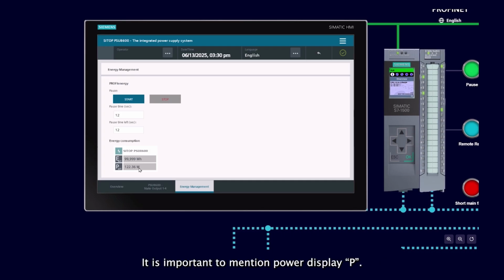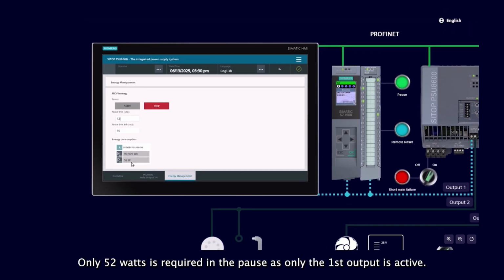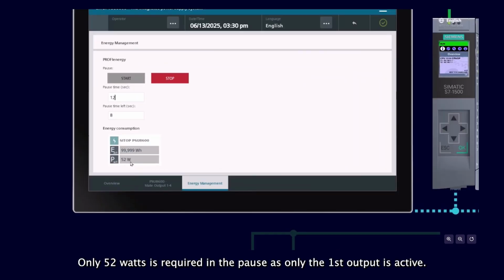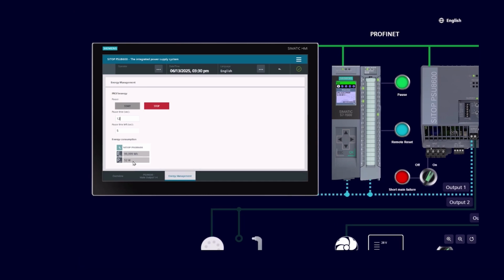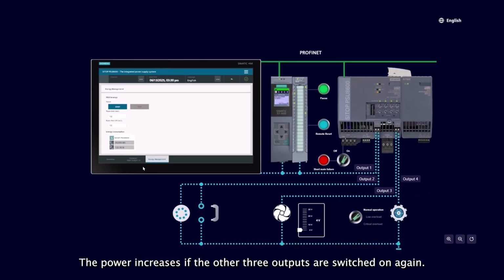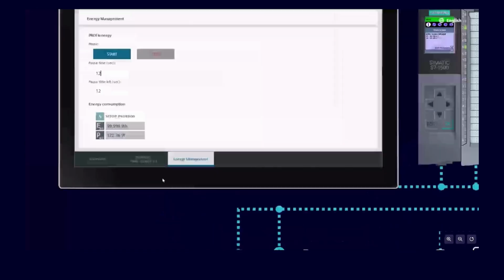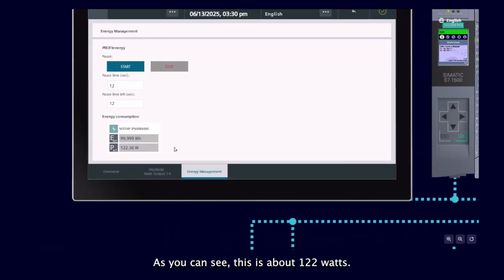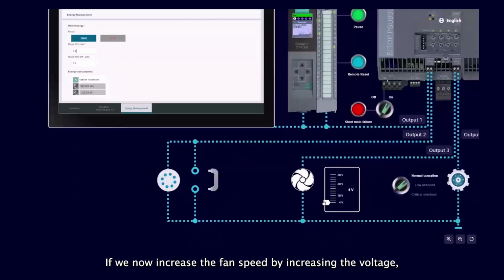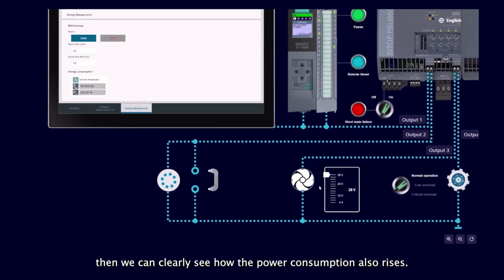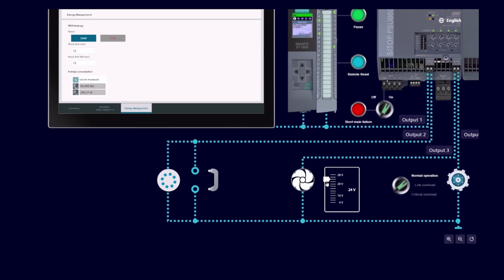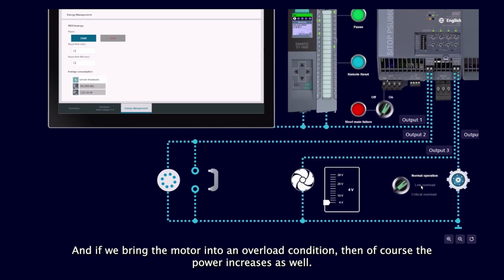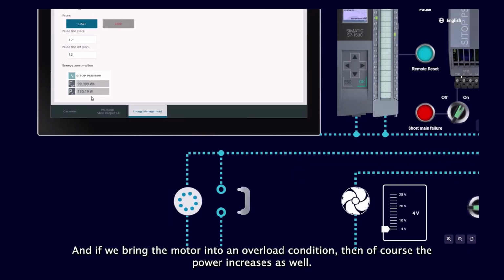It is important to mention Power Display P. Only 52 watts is required in the pause, as only the first output is active. The power increases if the other three outputs are switched on again. As you can see, this is about 120 watts. If we now increase the fan speed by increasing the voltage, then we can clearly see how the power consumption also rises. And if we bring the motor into an overload condition, then of course the power increases as well.